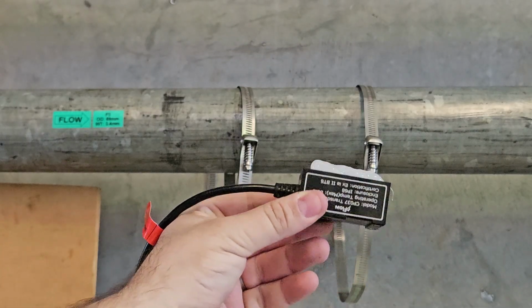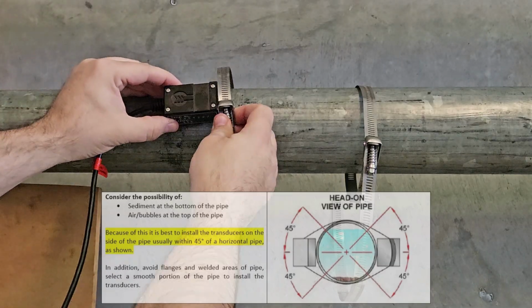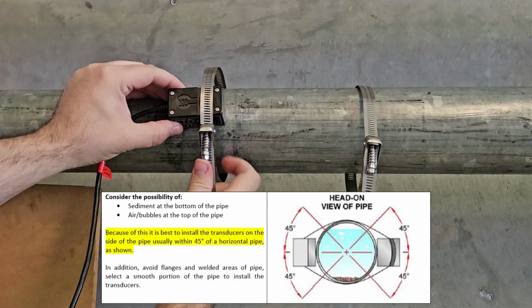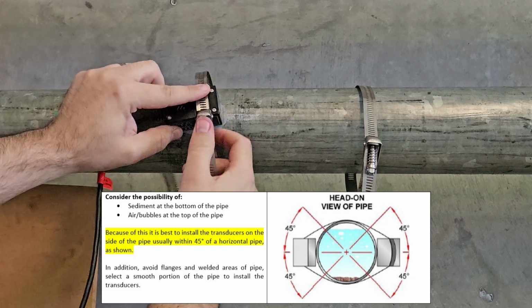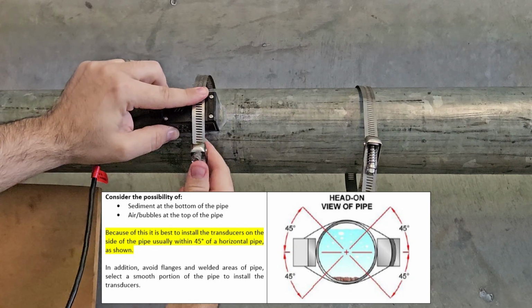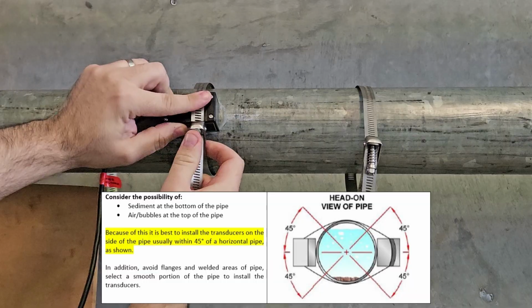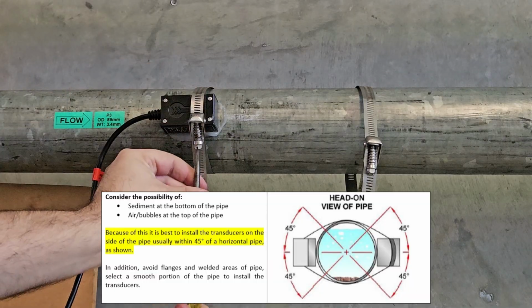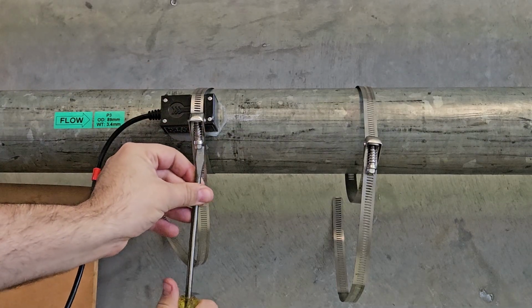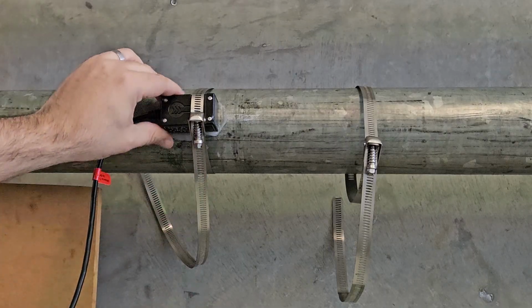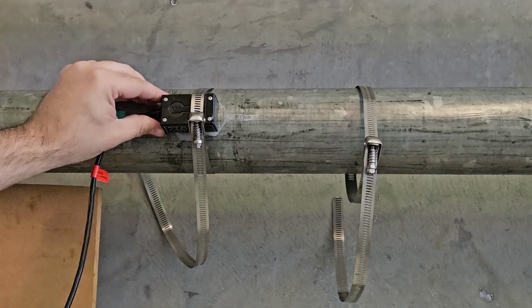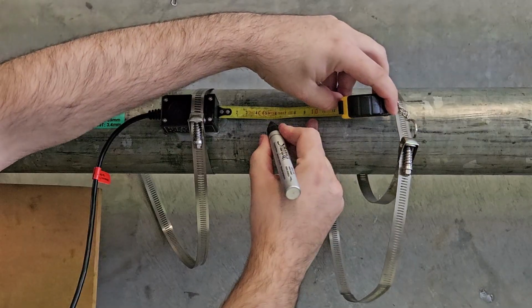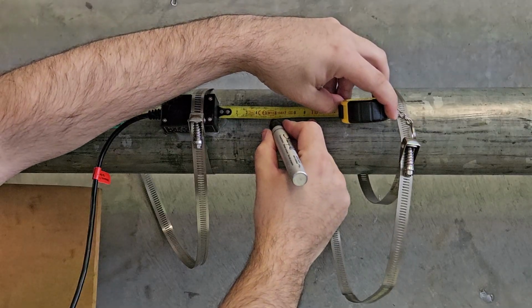Now, noting the flow direction, place the sensor onto the pipe and slide the strap over and tighten it down as best you can by hand. It's suggested to mount the sensors on the side of the pipe as shown, to avoid sediment at the bottom and air bubbles at the top. Now tighten the clamp with a tool and ensure it's firmly attached. Next, take a tape measure and measure out the required spacing which the meter displayed, and make a mark.